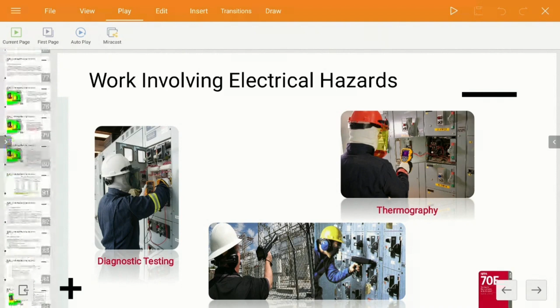This is that table I told you about, 130.4 EA. This is the table in the 70E that helps us determine those two approach boundaries for shock, our limited approach and our restricted approach boundaries. If you look in this column, it's all based on voltage. Your shock boundaries are just based on voltage, which arc flash boundaries aren't. So if you look at this table, between 151 and 750 volts, if it's an overhead conductor supported by a pole, our limited approach boundary is 10 feet. Makes sense, right? Got to stay 10 feet away from overhead conductors supported by poles. But if it's not, if it's anything above and beyond that, our limited approach boundary is 3.5 feet, and our restricted approach boundary is 1 foot.